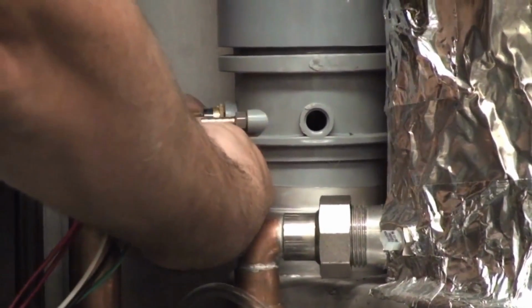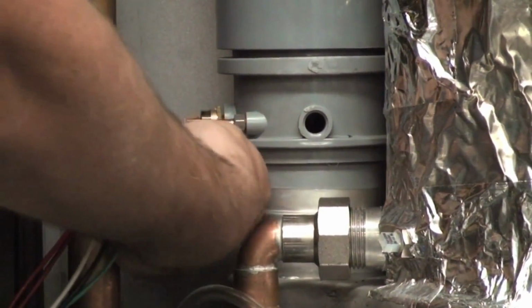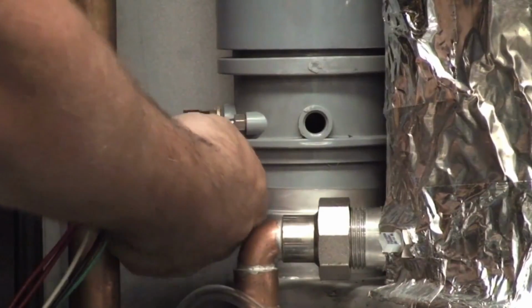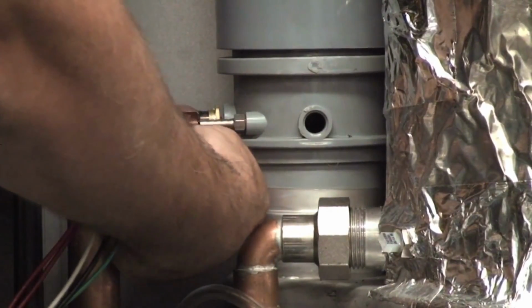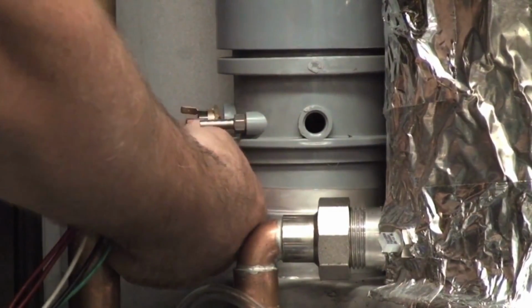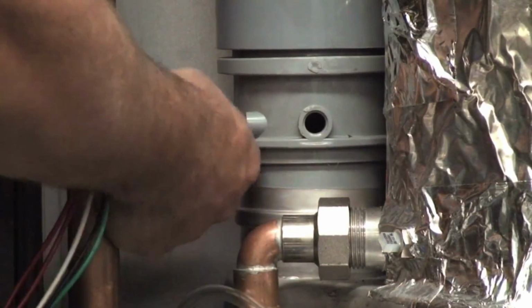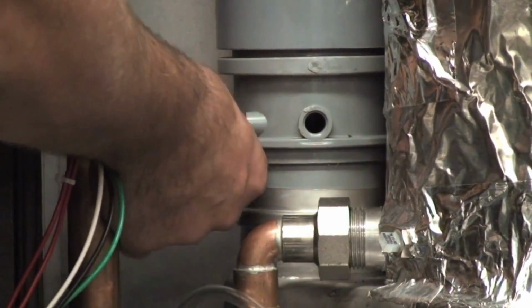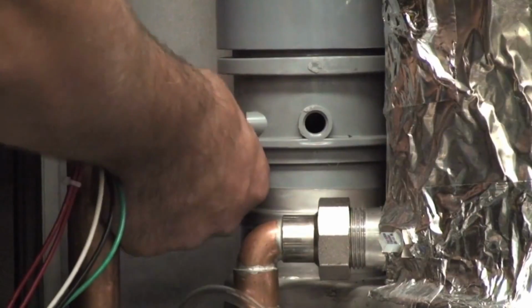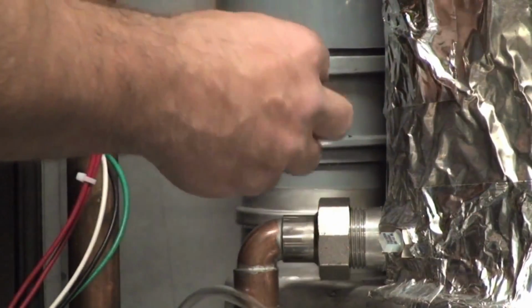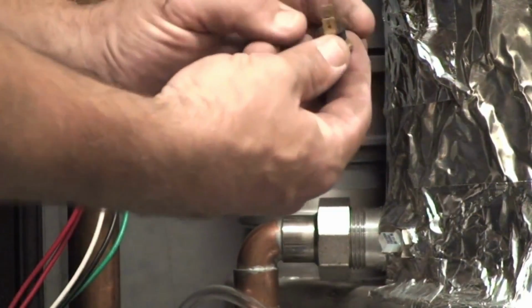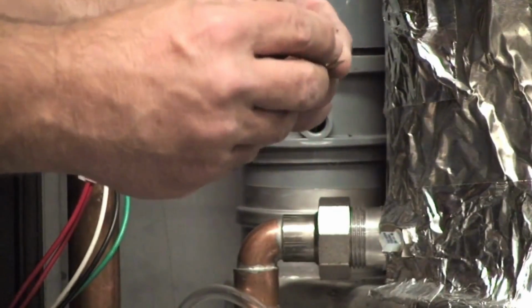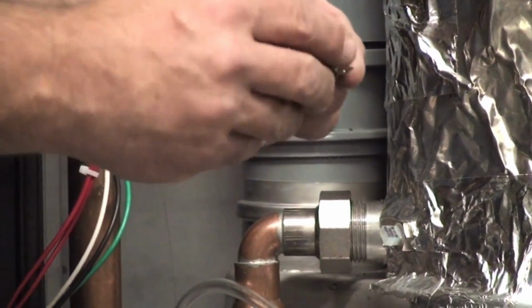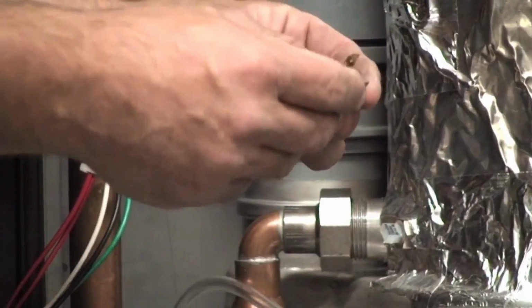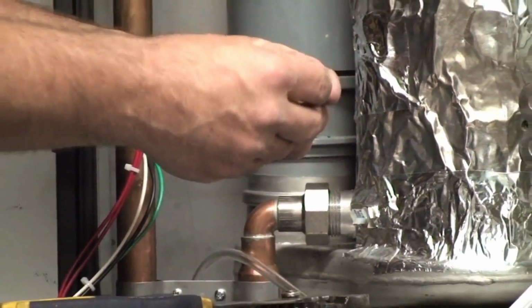Another sensor, which is a limit, monitors the flue temperature, and it's a safety limit just to make sure that for any reason whatsoever, if we start to see elevated stack temperatures above the limitation of the connected plastic material, that we will shut the unit down. The reset button is right here. So you have two leads, you run voltage through it, and that is a feedback back to the control.